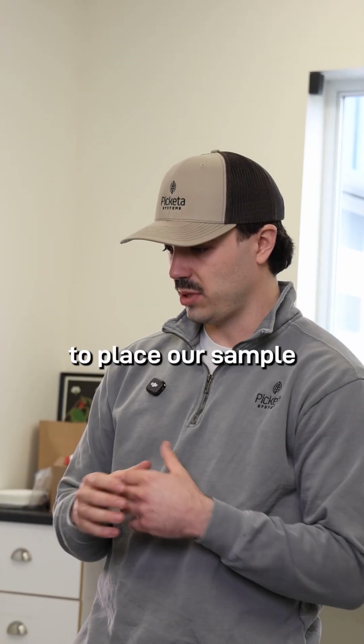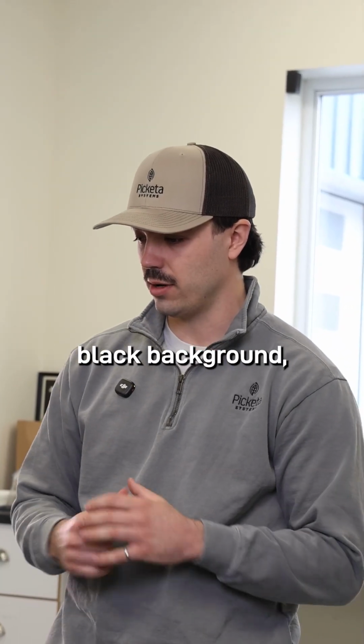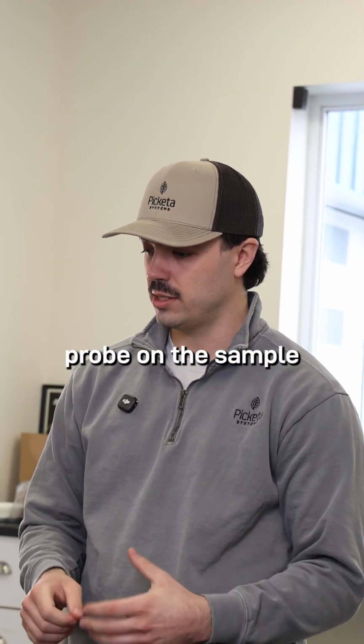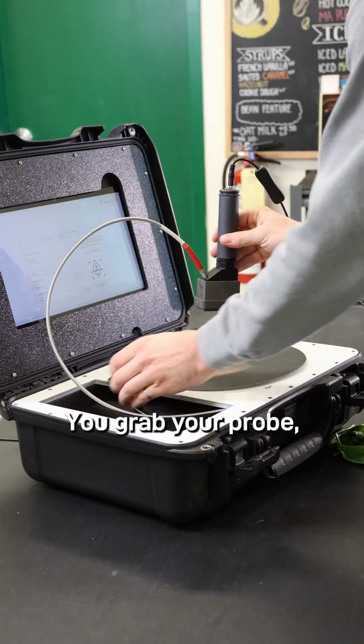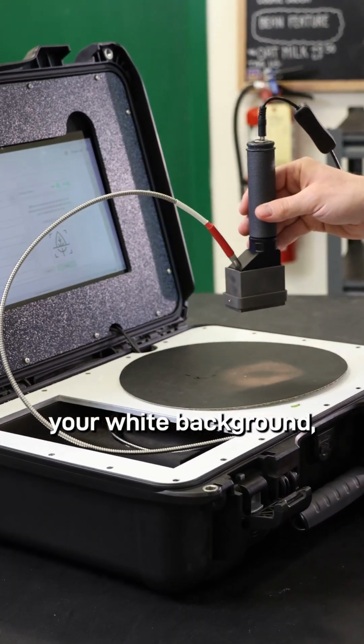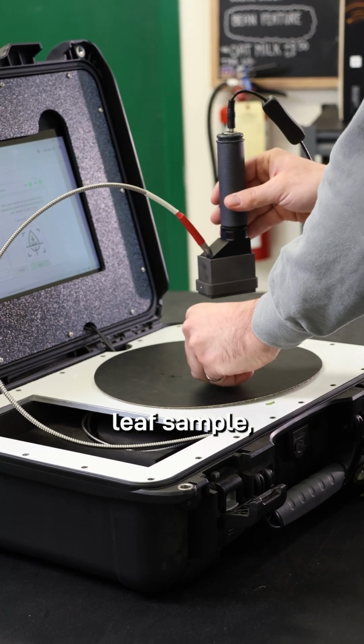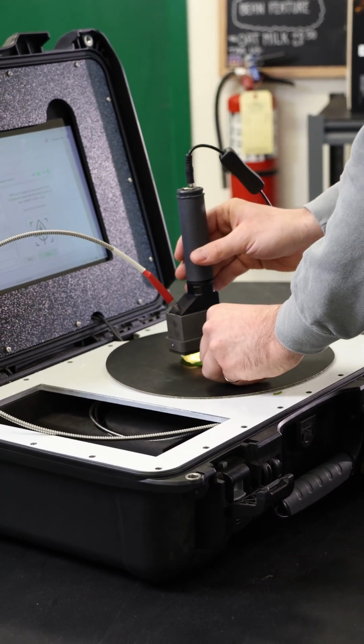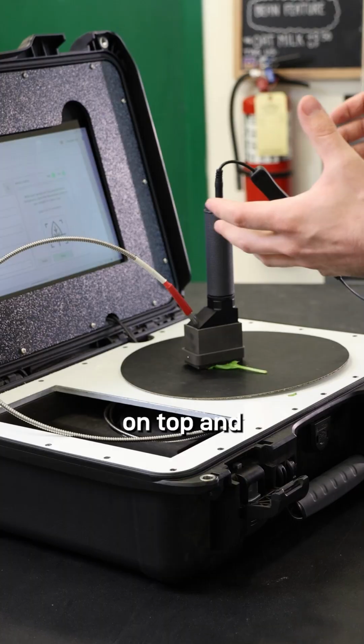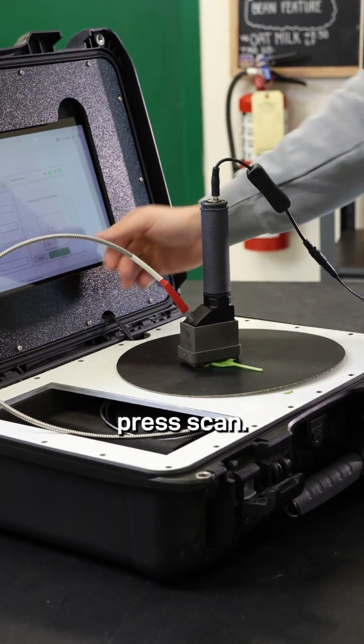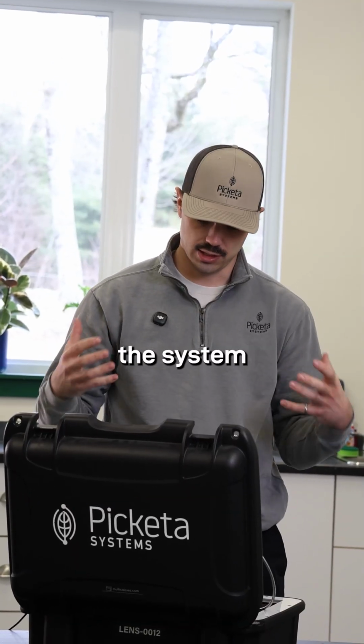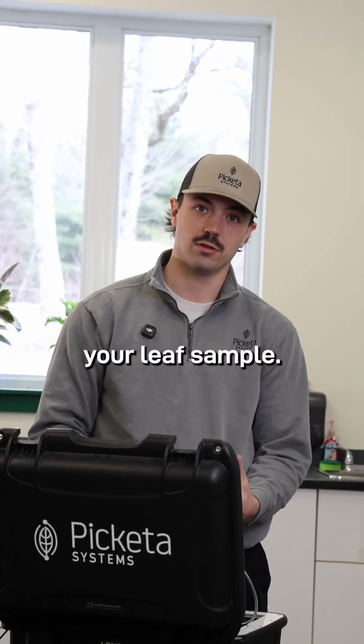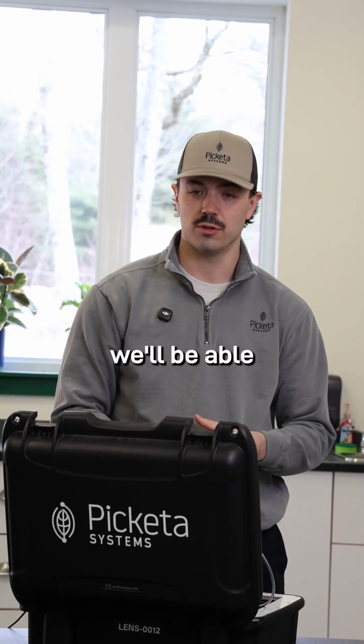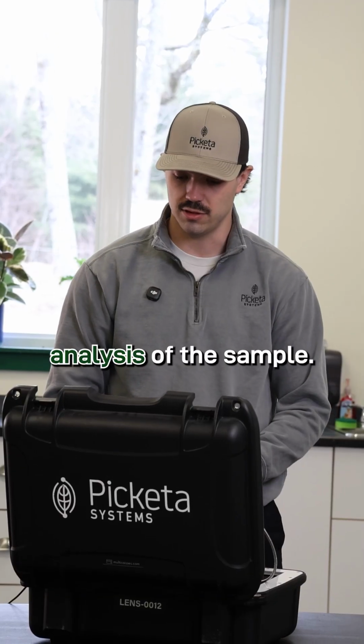It's asking us to place our sample on the provided black background and place the illuminated probe on the sample to take a scan. You grab your probe, take off your white background, grab your first leaf sample, place it on the scanning surface, place your probe on top, and press scan. So again, during this process, the system is going to evaluate how much light bounces off your leaf sample, and from there, we'll be able to give you a nutrient analysis of the sample.